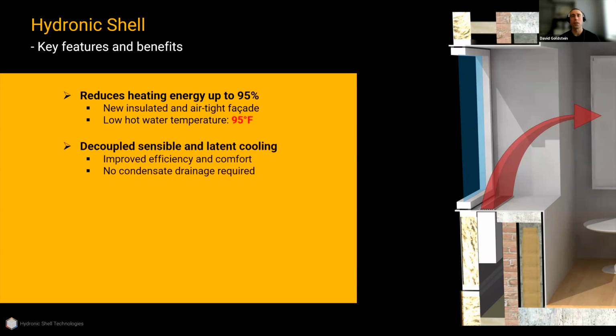We're also decoupling sensible and latent cooling. So that means that we're controlling temperature separately from humidity because we're using the ventilation air to control humidity. So it makes for much better efficiency and much better comfort out of the cooling system. And the other big advantage is we don't form condensate at the apartment level. So you don't have to worry about condensate drainage and running new condensate lines in your building to get rid of condensate.